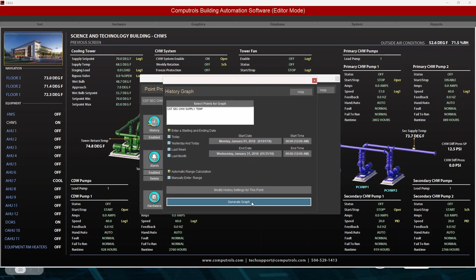If I want to start adding objects to this, I can simply come back up one step, select more points, and start to overlay things. So it becomes a valuable troubleshooting tool, right? I can see the call for compressor stage 1 and not a corresponding drop in supply temp. So now I know I've got a dead circuit. I can start to do some basic troubleshooting with this.